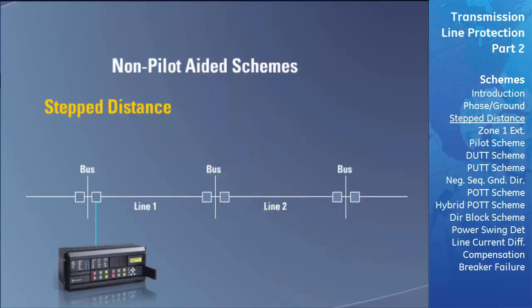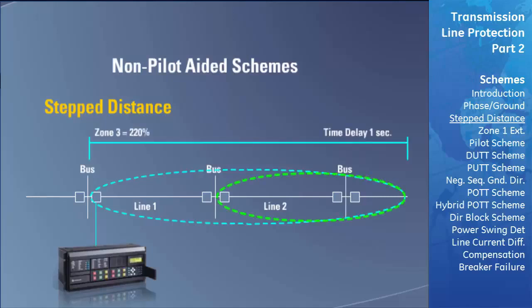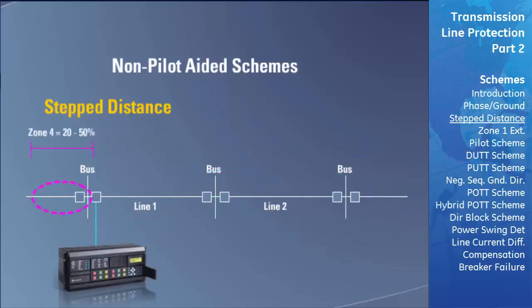The third zone of protection is set to overreach past the end of the second adjacent transmission line, acting as backup for that line in case its protection fails. Zone 3 is usually set to 220 percent of the impedance of its own line if line 1 and line 2 impedances are equal, extending to the same point as zone 2 of the adjacent line. Zone 3 must have a time delay longer than the operate time of zone 2 of the adjacent line—a time delay of one second is commonly used. Zone 4 provides backup protection for a small portion of the adjacent line in the reverse direction, with a typical time delay of 750 milliseconds to one second.